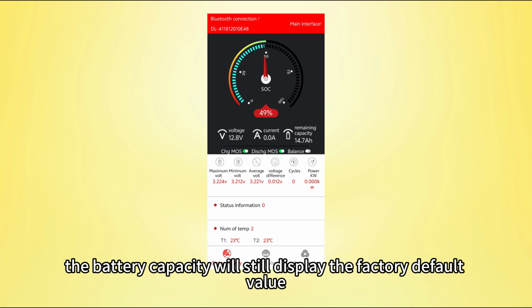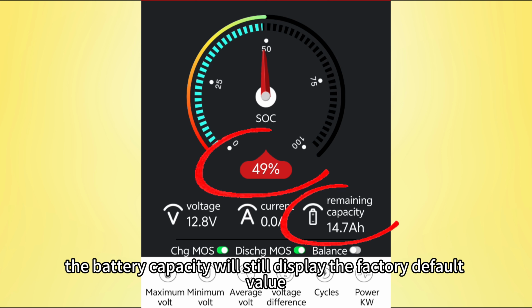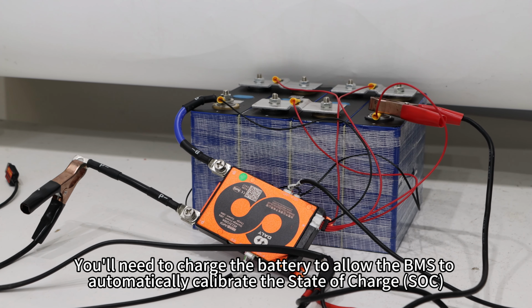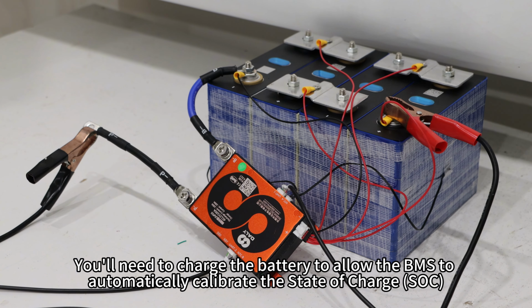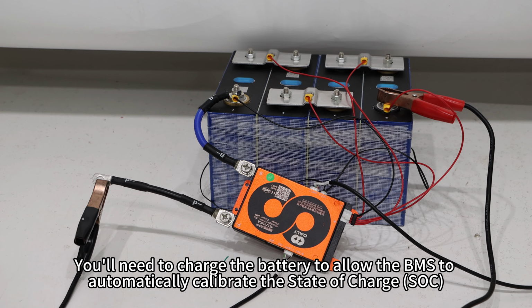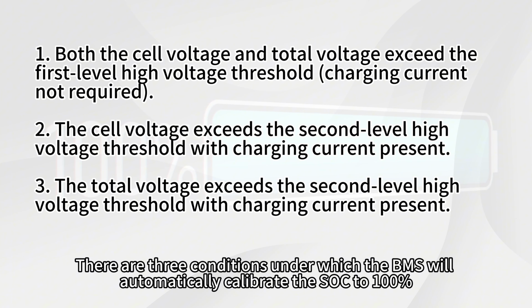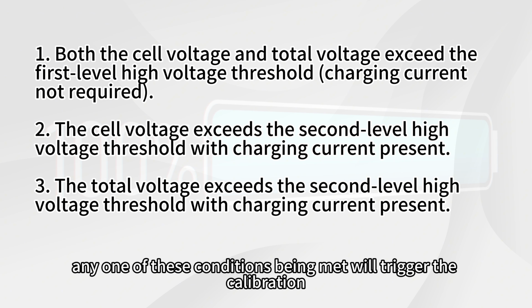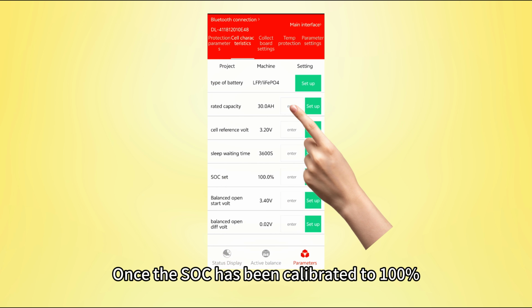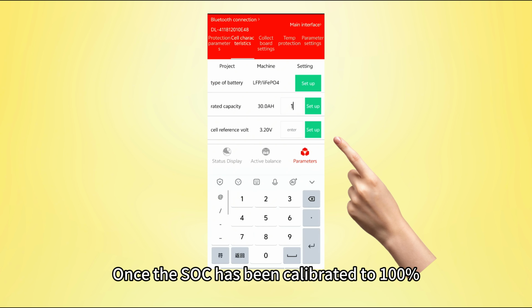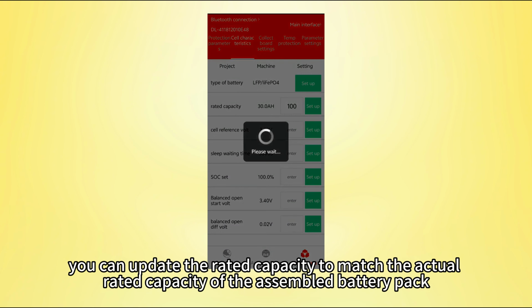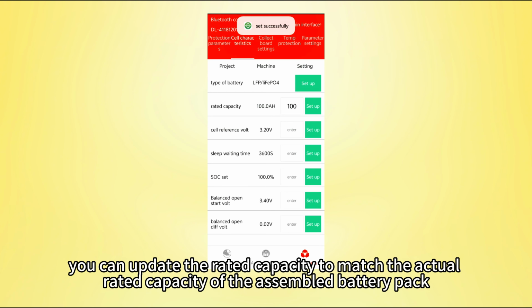At this point, the battery capacity will still display the factory default value. You will need to charge the battery to allow the BMS to automatically calibrate the state of charge. There are 3 conditions under which the BMS will automatically calibrate the SoC to 100%. If any one of these conditions is met, it will trigger the calibration. Once the SoC has been calibrated to 100%, you can update the rated capacity to match the actual rated capacity of the assembled battery pack.